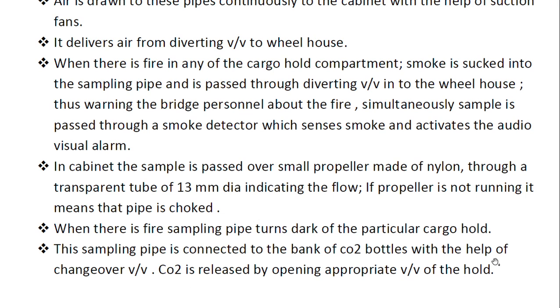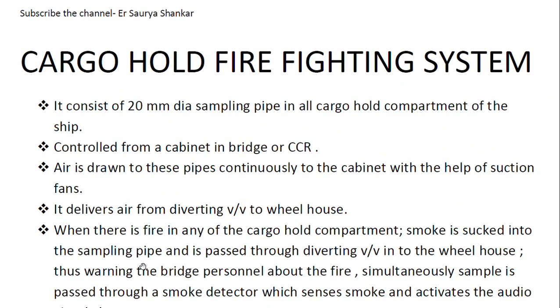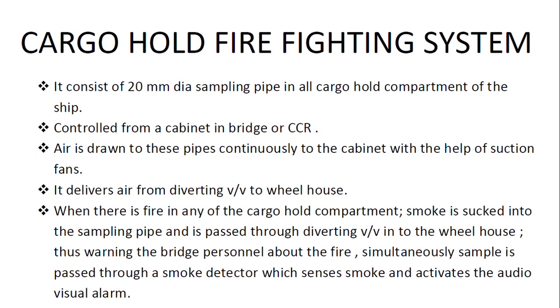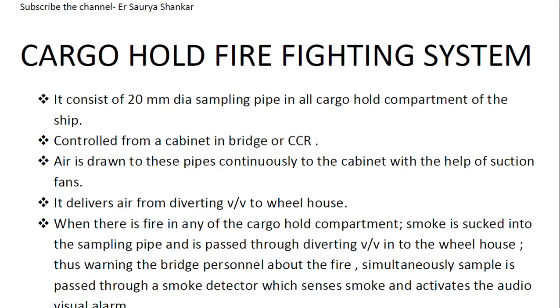This sampling pipe is connected to the bank of CO2 bottles via a change-over valve. CO2 is released by opening the appropriate valve for that hold. With the change-over valve, the CO2 bottle is operated to discharge CO2 into the particular cargo hold. In summary: for cargo hold firefighting we have a fixed CO2 system, smoke detectors, a 20 mm sampling pipe continuously drawing samples to the bridge, a nylon propeller and transparent tube in the cabinet, and with the change-over valve CO2 can be discharged into the affected cargo hold.